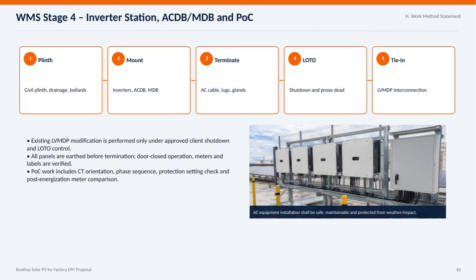Here we outline the key steps involved in the WMS Stage 4 for the inverter station, ACDB, MDB, and point of connection. First, the civil plinth needs to be constructed with proper drainage and bollards for protection. Next, we mount the inverters, ACDB, and MDB carefully on this foundation. Then, termination of AC cables, including lugs and glands, is performed to ensure secure electrical connections. A critical safety procedure is the lockout-tagout process to shut down the system and verify it is completely de-energized before any work proceeds. Following this, the tie-in to the LVMDP is conducted, but only during an approved client shutdown and under strict LOTO control to maintain safety. It's important to confirm that all panels are earthed before termination, and that meters and labels are accurately verified with doors closed to prevent hazards.